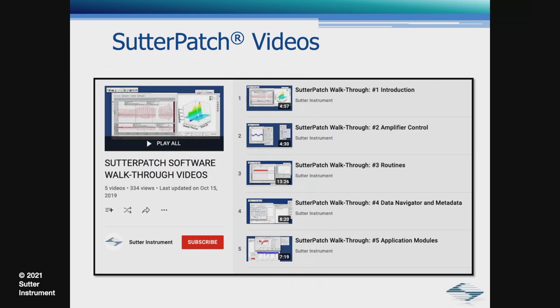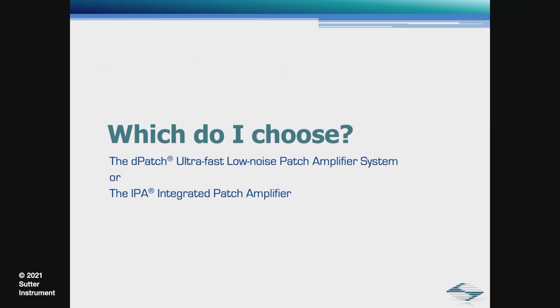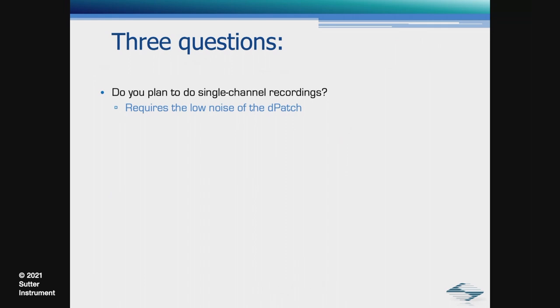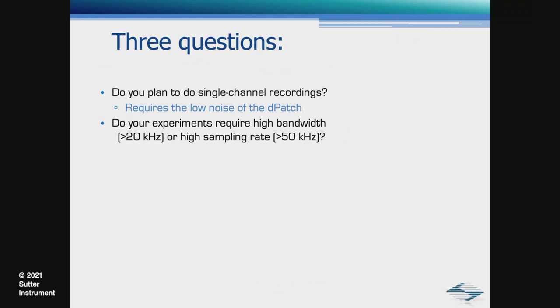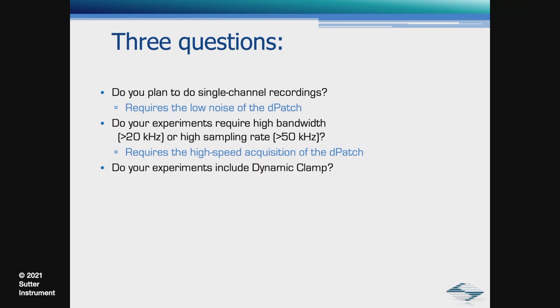Now we have choice of amplifiers. Which one do I choose? Typically, we ask three questions. Do you plan to do single channel recordings? Then the low noise option of the D-Patch is probably what you need. Do your experiments require bandwidth that is greater than 20 kilohertz and higher sampling rate greater than 50 kilohertz? Then the D-Patch would be a better choice. Finally, do your experiments include dynamic clamp? Well, the D-Patch is the only commercial amplifier out there that has this option. My colleague, Jan, will talk about dynamic clamp option in detail in his talk.